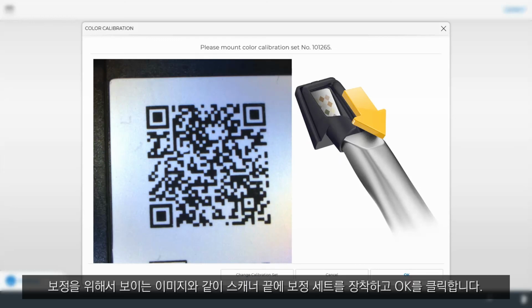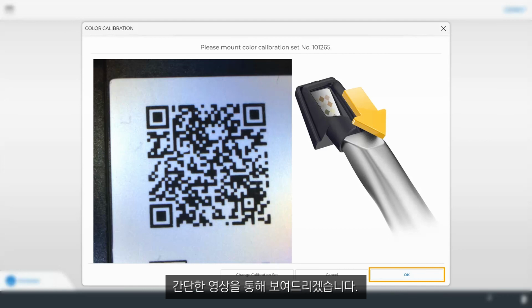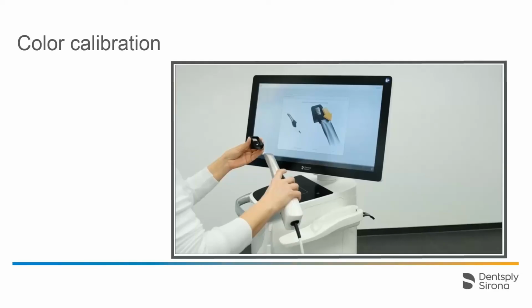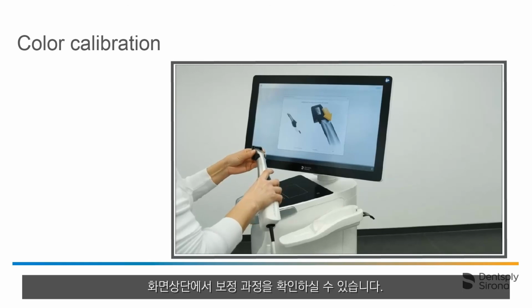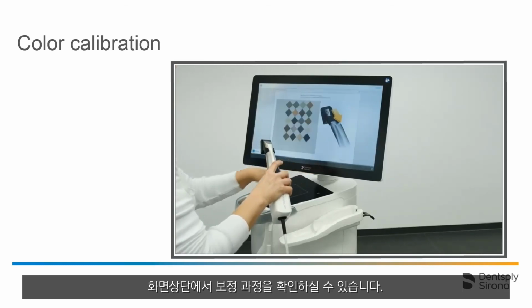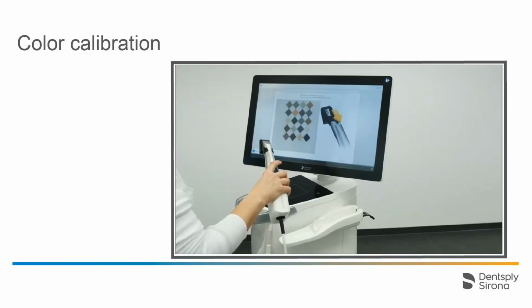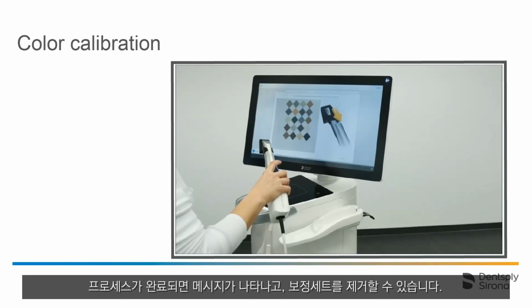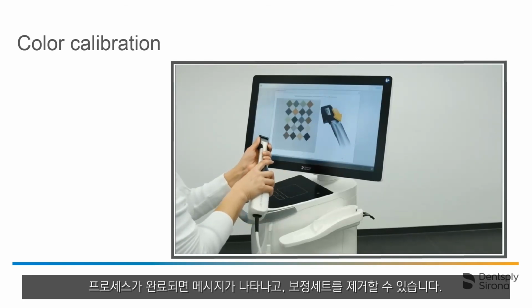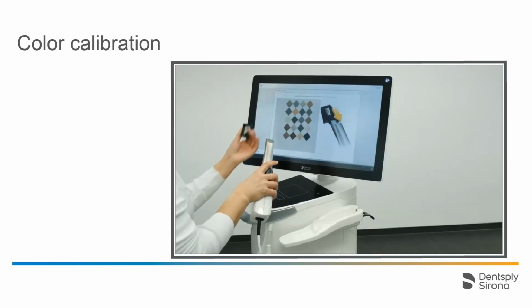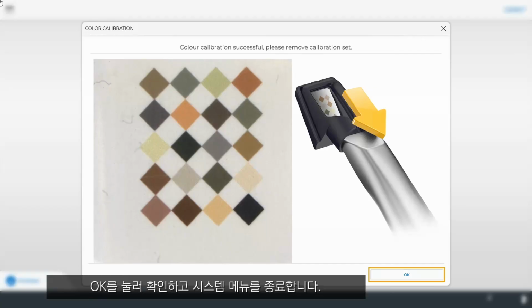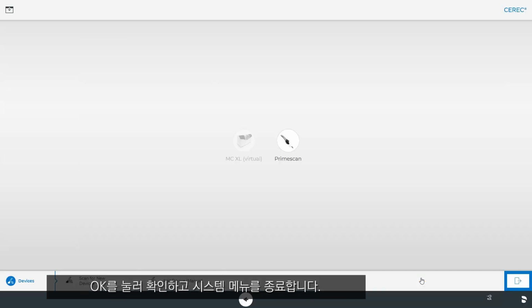To do so, mount the color calibration set on the tip of the scanner as shown in the illustration. Then click OK. Let us take a look at a short demonstration video now. At the top of the screen, the progress of the calibration is displayed. Once the process is complete, a message appears, and you can remove the set. We confirm with OK and exit the System menu.